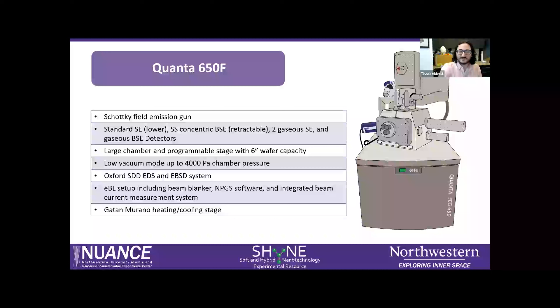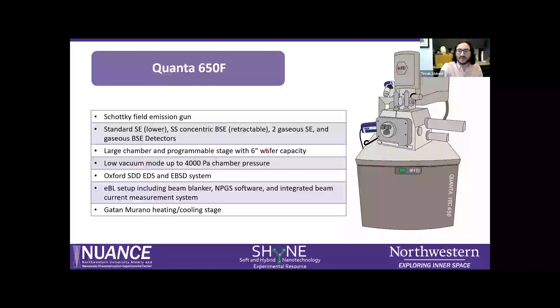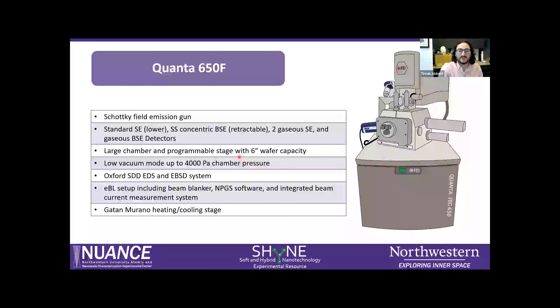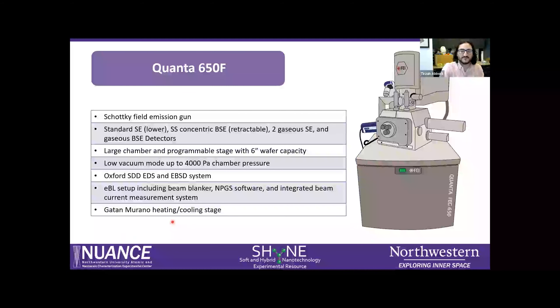The Quanta 650F is also a Schottky field emission gun with an extensive array of detectors: a standard lower secondary electron detector, a solid-state concentric backscatter detector (retractable), two gaseous SE detectors, and a gaseous backscatter detector. It has the largest specimen chamber of all our SEMs and a programmable stage that can move in steps for large-area analysis. Low vacuum mode can increase pressure up to about 4000 pascals. It has an EDS detector, an EBSD detector for electron backscatter diffraction, an EBL setup with beam blanker, NPGS software, and an integrated beam current measurement system, plus the Gatan Murano heating stage and a cooling stage for in-situ experiments.